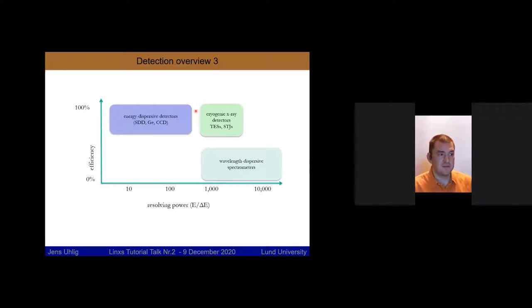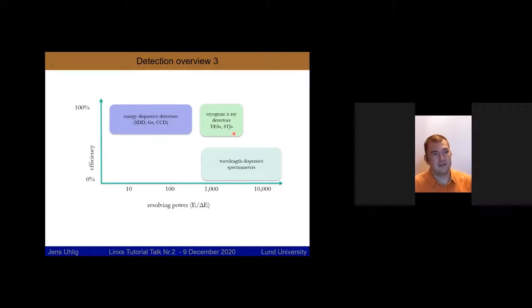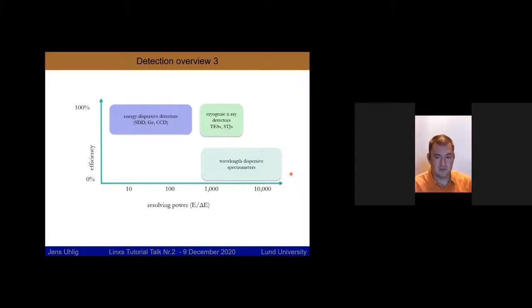To summarize detector types: energy dispersive detectors such as silicon drift detectors, CCDs, or germanium types give resolutions of about 100 eV at 6 keV — enough for XRF but not high-resolution science. Cryogenic detectors are very efficient with high resolution but are rather expensive. The third group, most likely used in the lab for high-resolution spectroscopy, is wavelength dispersive spectrometers.